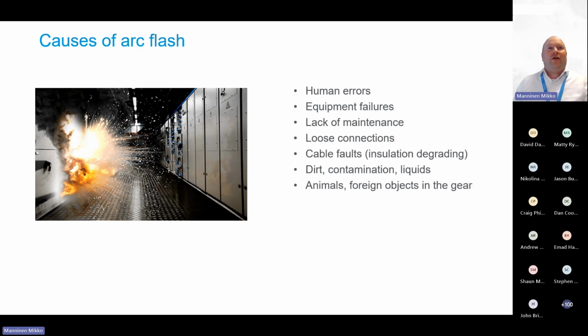I can tell one human error example. This happened in a nuclear plant. There was an electrician with a torque wrench, and he had an extension part for the torque wrench. He was tightening the L1, L2, L3, all three phases, and the bus bars on top of the main circuit breaker. Finally, he also had to torque the bolts for the neutral. He had to remove the torque wrench extension part and did the neutral with the shorter torque wrench, and he put the extension, let's say, in the wrong place. And he forgot it, but it was somehow in a safe area, not on top of the bus bars.